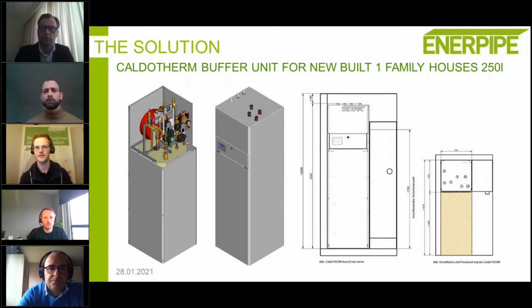And also, if you don't have a domestic hot water boiler installed in each house, but instead have a combined heat interface unit with two heat exchangers, you have hot water on the station all the time. So there's also constant temperature on the plate heat exchangers, which has a lot of heat losses as well. So really, both concepts should not have a big difference in heat losses. There's also a difference if you have the heat stored inside the house - this effect makes much more sense in winter than in summer, but it's not lost energy, which is the problem you have with pre-insulated pipes underground.